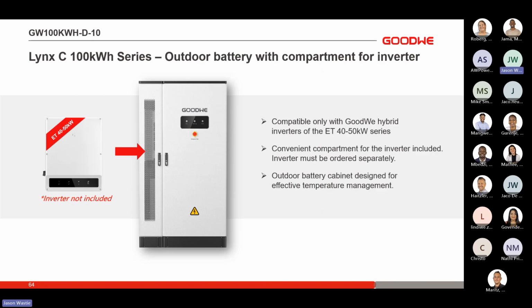So this battery series will be compatible with our ET series. The outdoor battery cabinet is designed for effective temperature management, so through the air conditioning. Obviously, we are very wary of having anything outdoors at the risk of it finding feet overnight. So one of the things that make this outdoor casing as impressive as it is, is the design being as rigid and protected. You could essentially have it in your building on the floor, rather than having to build a separate room for your batteries and inverters.